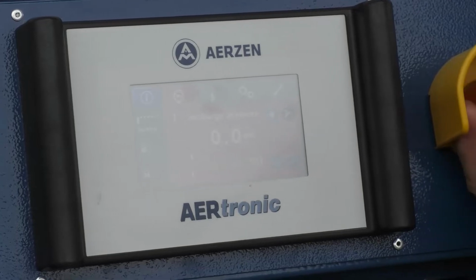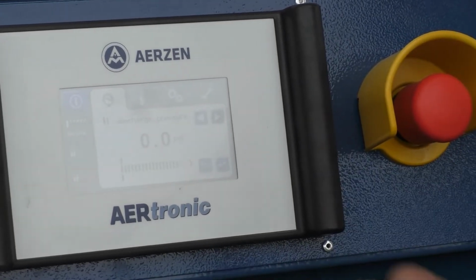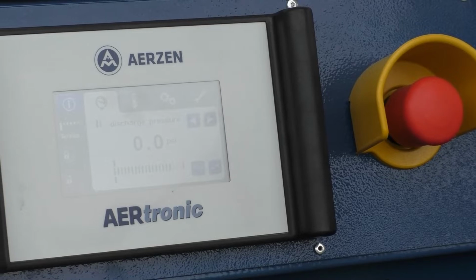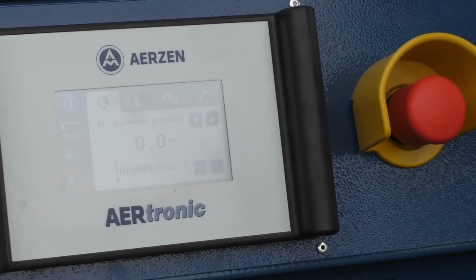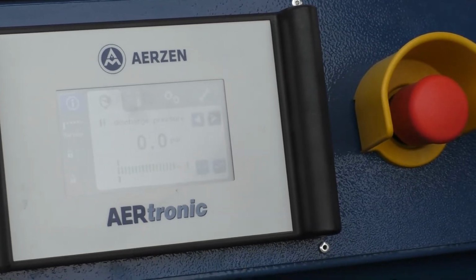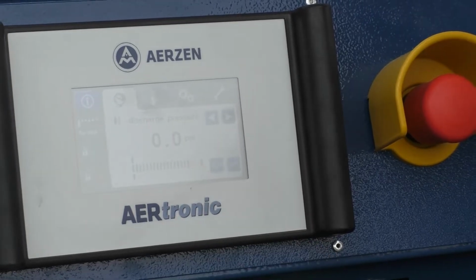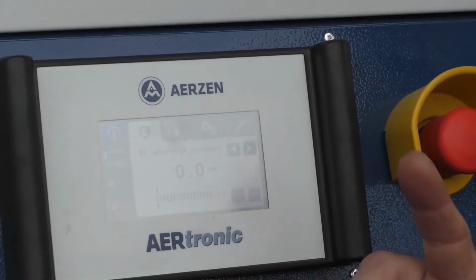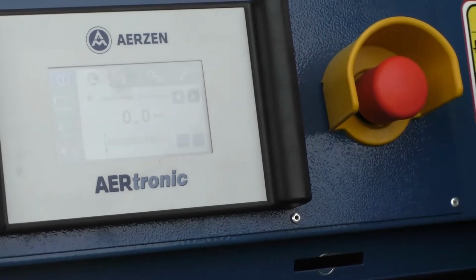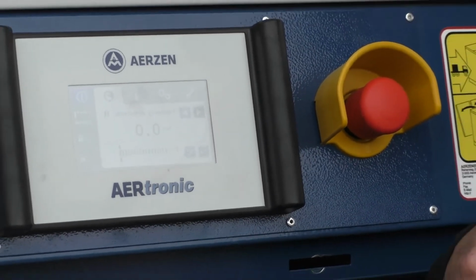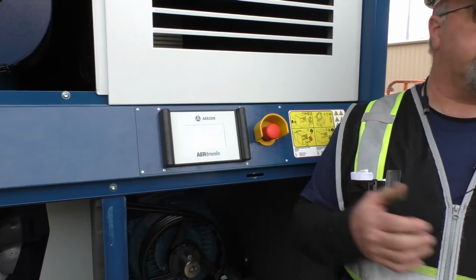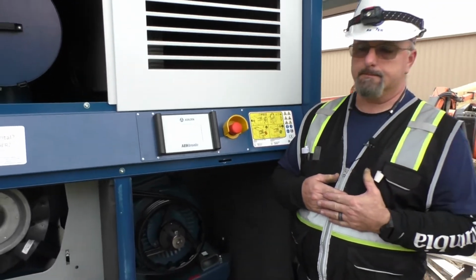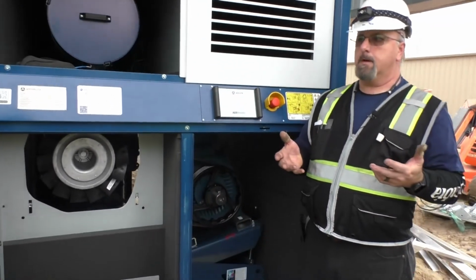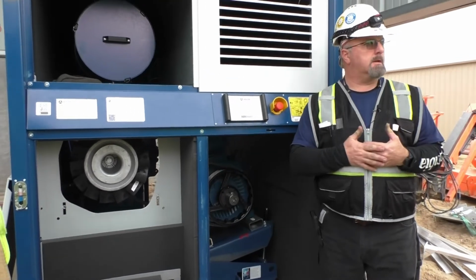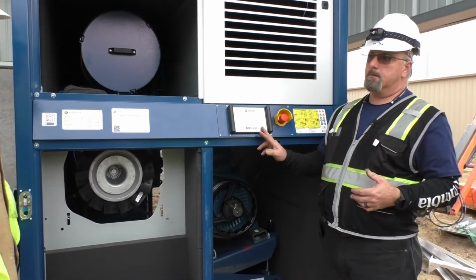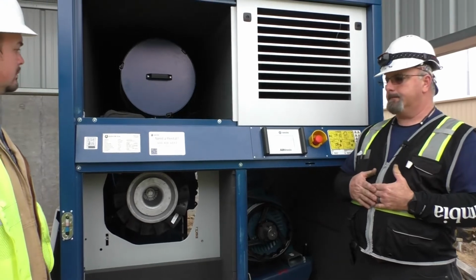Now if I pull this e-stop out, there's no more fault, it went back to a normal screen. So until that fault is actually cleared, you will not be able to put the blower back into operation. That screen will stay red, the fault circuit's still active. Hence, even with the temporary alarm, that will prevent the blower from restarting. Once SCADA goes into effect, it's going to be the same thing because it's picking up that same general fault and relaying that to the drive.